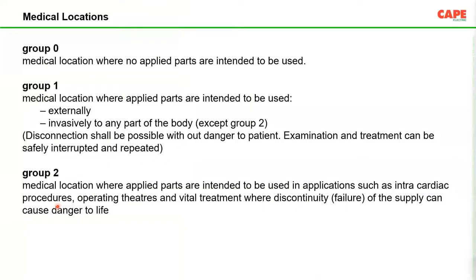Now, medical locations are classified into group 0, group 1 and group 2 medical locations. Group 0 medical locations are where medical electrical equipment can be brought into contact with the patient or touched by the patient, but the applied parts are not intended to be used. Medical locations where no applied parts are intended to be used are called group 0 locations, but it doesn't mean that the person is not allowed to touch the electrical appliance. Yes, of course, that is allowed.